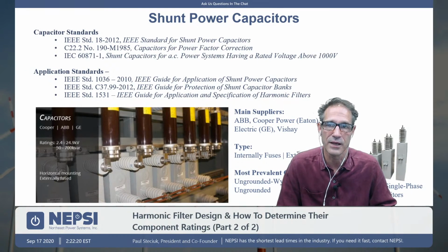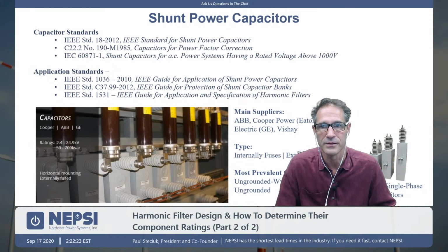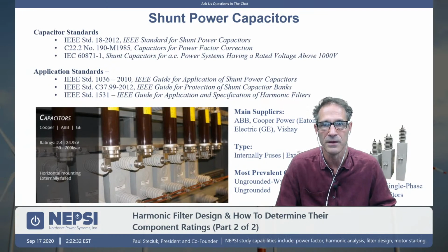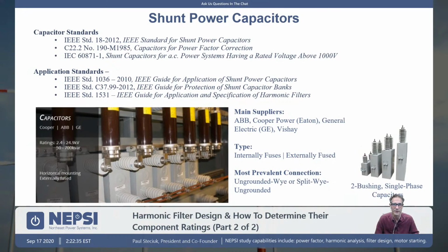There are some application standards. IEEE standard 1036, dated 2010, is a guide on the application of shunt power capacitors. It's a good reference for those that are looking to get more information. You've got IEEE C37.99, 2012, the protection of shunt capacitors, which is another good standard. And then IEEE 1531, guide for the application and specification of harmonic filters. So for us, the main suppliers are primarily ABB, Cooper, General Electric. I do mention some others. Vishay is a very popular capacitor supplier also that we have encountered in years past.